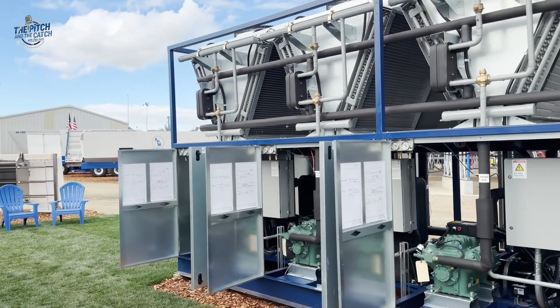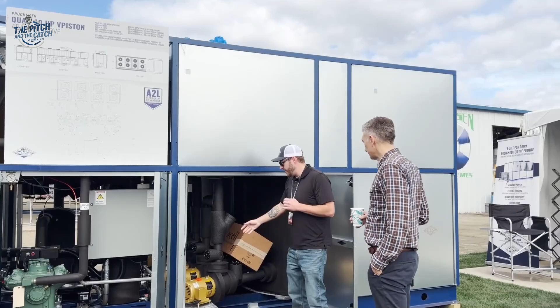We do the same with the compressor. When we size one of these units, if it's a 4 compressor unit, we want 3 compressors to handle the whole load, and that 4th circuit is a full redundant. Same with the pumps.